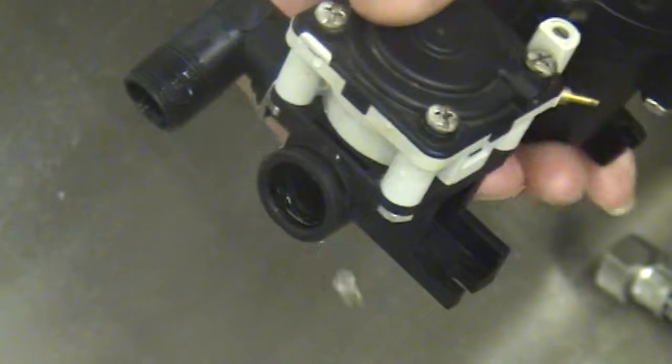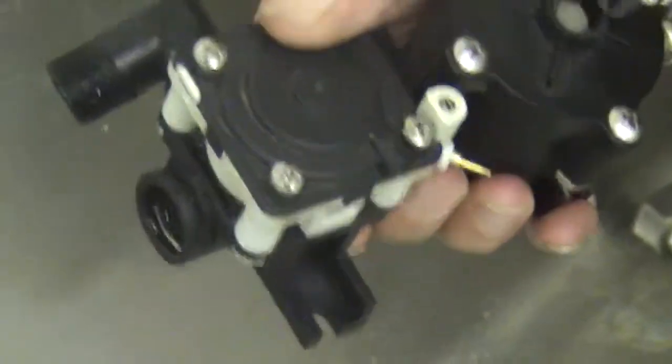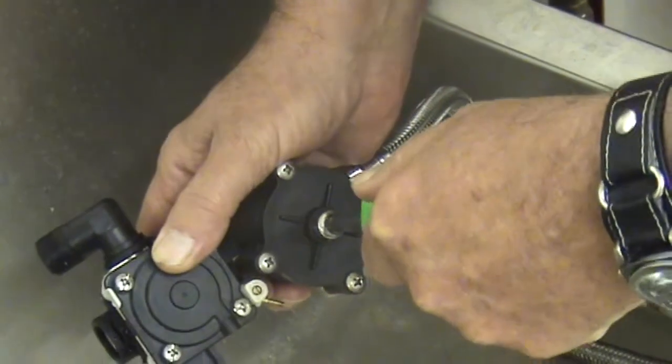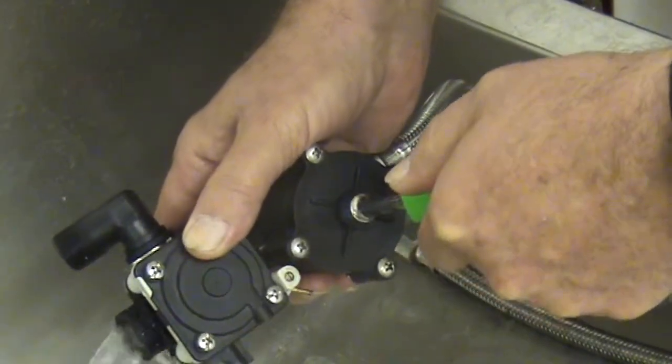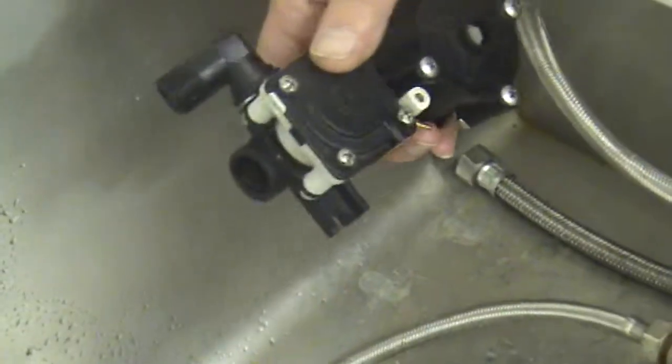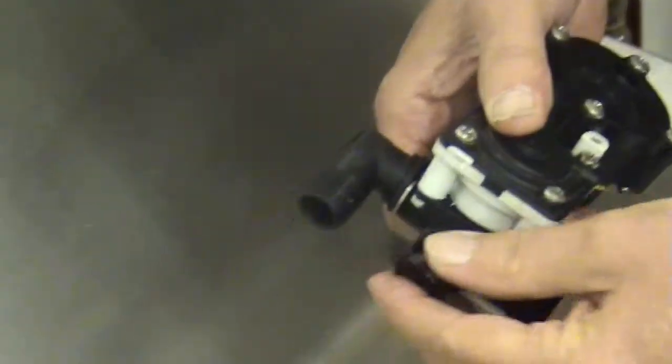Now, the next test, we open the check stop just slightly to make sure that we're getting water through the valve. If we're getting water through the valve, we know the check stop is okay at that point. So we can reassemble this.